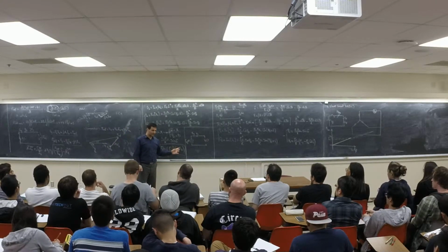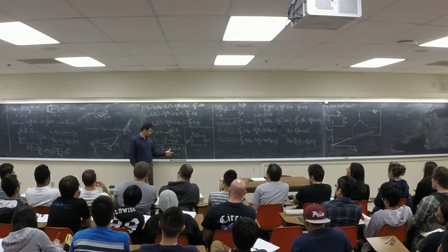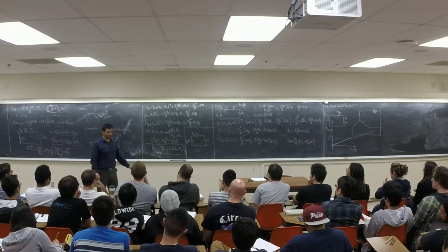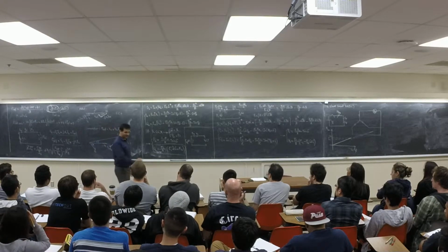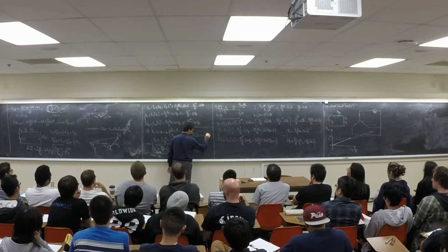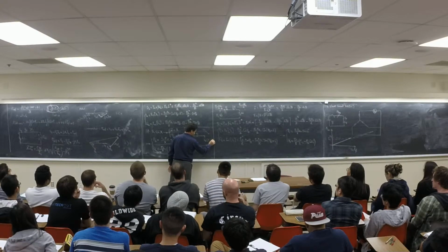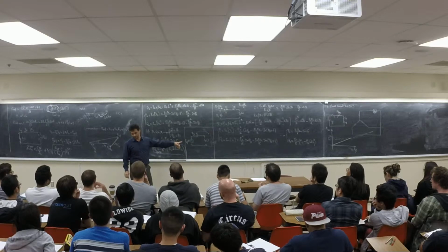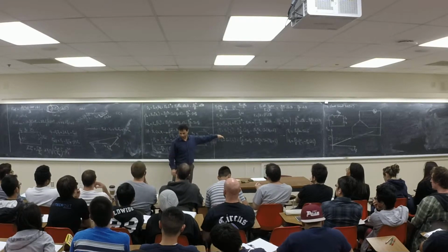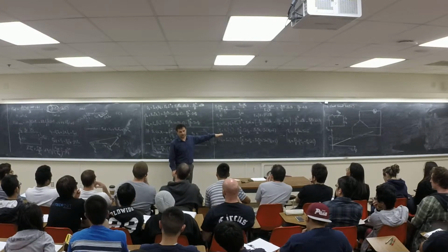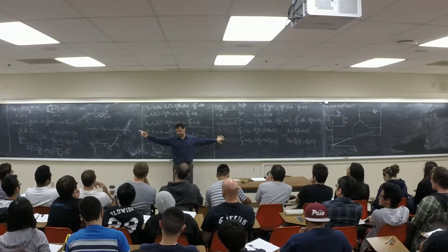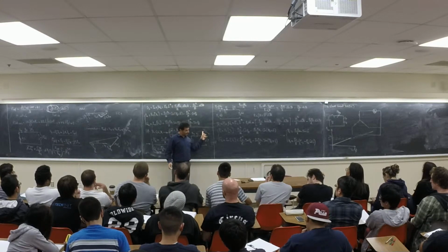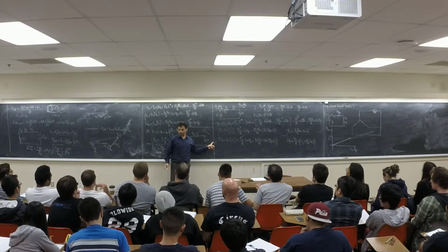Look at this Q2. It could be positive, it could be negative. If this one is more than this, it's positive. If this one is less than this, it's negative. If Q2 is positive, what does it mean? I'm sending reactive power this way. Think about it. It's like an inductor, right? You're supporting reactive power here, so you can do power factor correction. Let's say you remember from power systems, you have a power factor you want to correct. You need something to generate reactive power. So here I can inject reactive power and improve the power factor of my system.